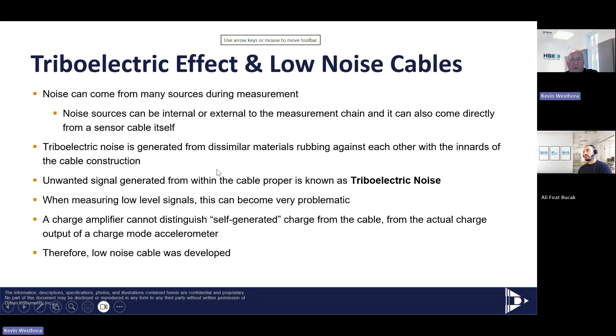All right, next thing I want to do is talk a little bit about noise. I'm going to skip this screen. There's too many words here. I'm going to skip this screen as well and go right to this video. This is a really good video to talk about making sure that you have the proper cable with the accelerometer that you're purchasing. So in the Dytran world, white cables are IEPE voltage mode cables. Red cables are low noise charge mode cables. So in this video, I have a charge mode accelerometer with a white IEPE cable. It's the wrong cable, and you're going to see what's happening.